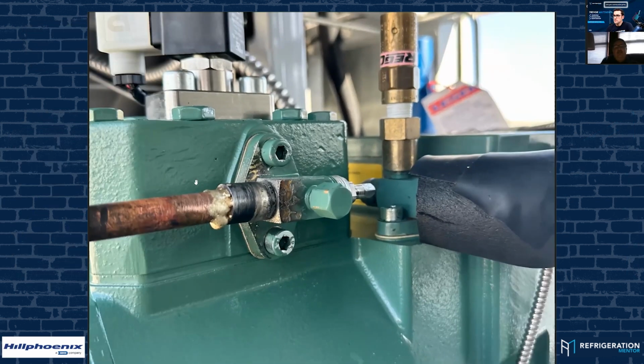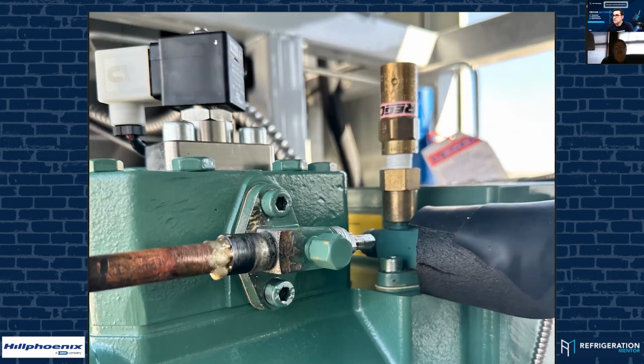We converted a mini flex from a VFD to a digital on the low temp to get more suction capacity, and we had to change the valve out because the valve is actually bigger for the digital head. But the brazing technique could have been better. Definitely brazing technique there. But it was nothing against the contractor. We were in a tight situation. We didn't realize until we actually tried to put the old line back on the new head that it was undersized. So we were in a time constraint.